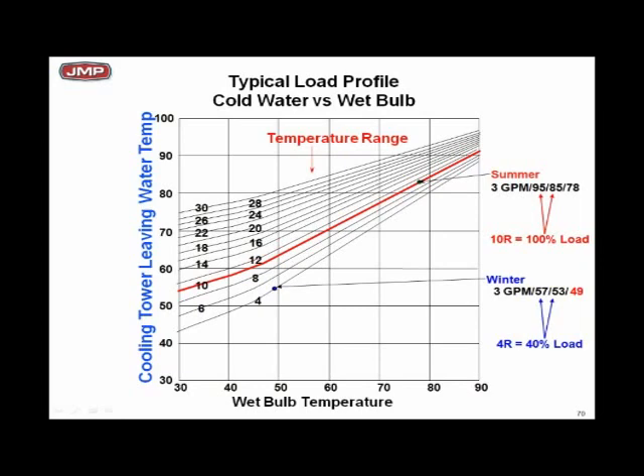And normally we pick a tower, nominal design. It's 78-degree wet bulb, which is what we call the summer condition here. It's 78-degree wet bulb, 10-degree range. So the first point we picked was a 10-degree range, by the way, is 3 GPM per ton. 15,000 BTUs, 3 GPM per ton, 10-degree range.